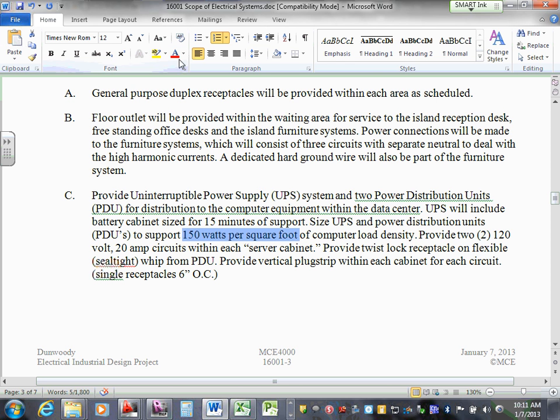That's how data centers often get designed, because IT groups don't always know exactly what's going in, but we track the trend of loads within these data center environments, dating back to the early 80s when we were looking at 20 to 25 watts a square foot, then slow growth. We've done data centers over 200 watts a square foot, and in fact one at 300 watts a square foot. That's getting pretty dense - that's a lot of heat, but that is the trend.